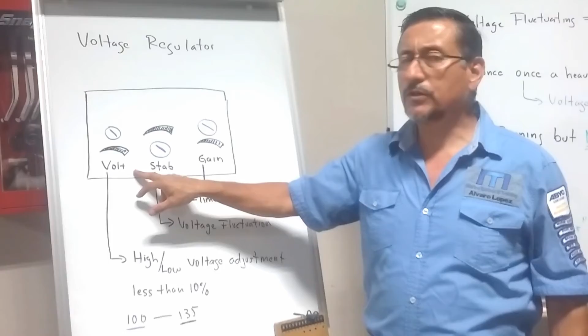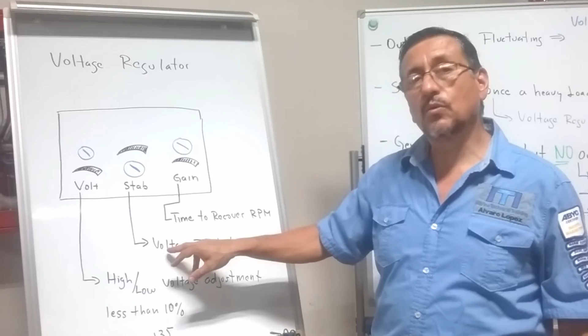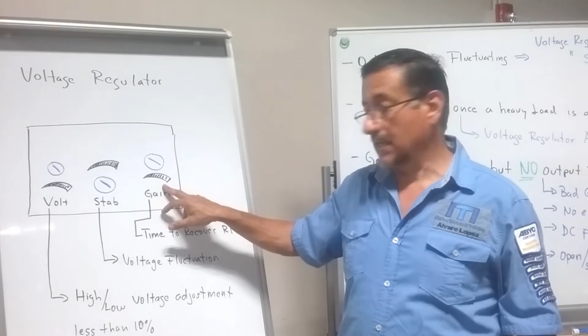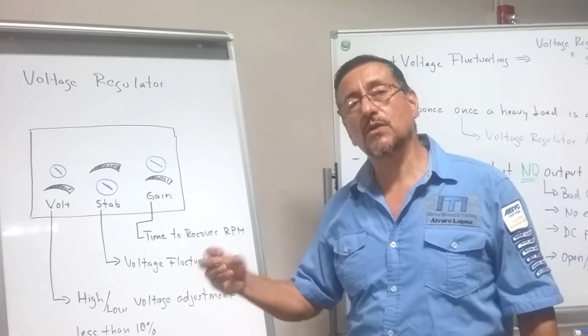The first spot is for voltage, to calibrate high or low output voltage, no more than 10%. The second one is stabilization, to verify fluctuation in the output. And the third one is the gain. That spot is used to calibrate the response of the engine when the load is applied.